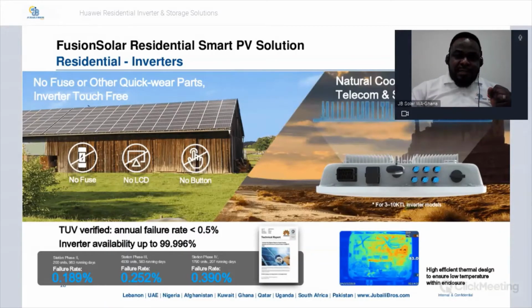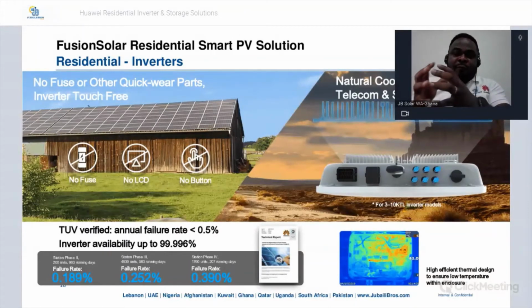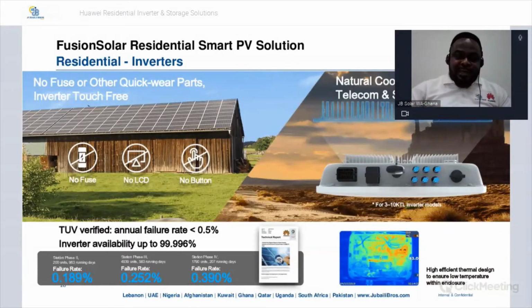That's why we have moved all the O&M onto your phone, so you can have access to the KPIs. In place of the fans, we have a heat sink located behind the inverter. If you take a look at the thermograph, Huawei has carefully separated the heat generating part of the inverter from the heat sensitive part. These are two key things. The colder part of the inverter is the heat sensitive area, and it has been separated on one side from the heat generating part on the other side. So the components are not all mixed together, which would let the heat generated destroy the heat sensitive areas. We also have a heat sink at the back of the inverter to cool the system as production is ongoing. This is the technology that we have here.